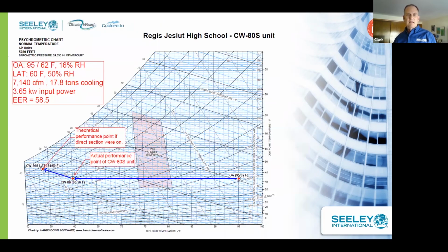Now, the next slide, I'll show you a little bit of the psychrometrics. On that day, we were at 95/62. We were cooling the air down to 60 degrees, doing sensible cooling. And this unit is actually a super cool unit, so it has a direct evaporative pad. But the air was cold enough, they didn't even need to turn on that direct evaporative pad, but they could have gotten a few more degrees out of the unit if they wanted to.